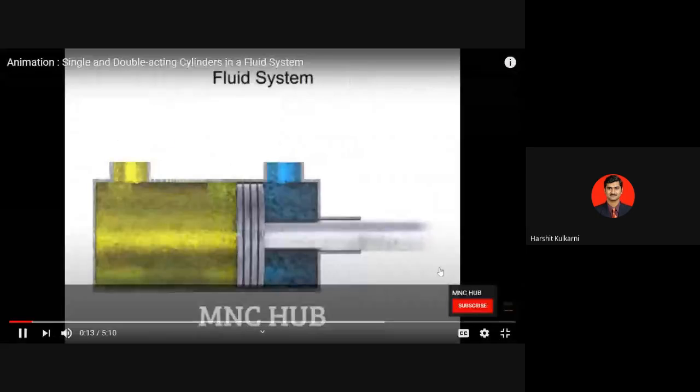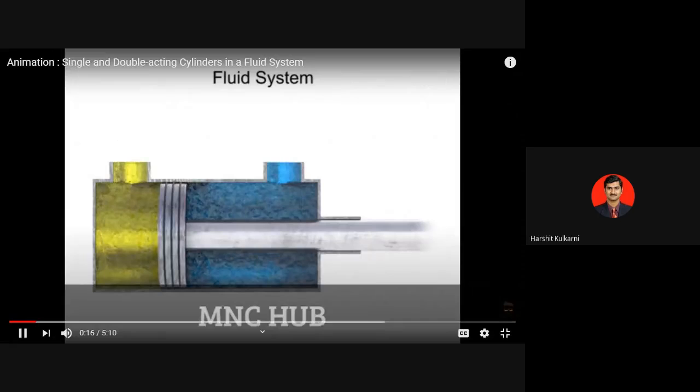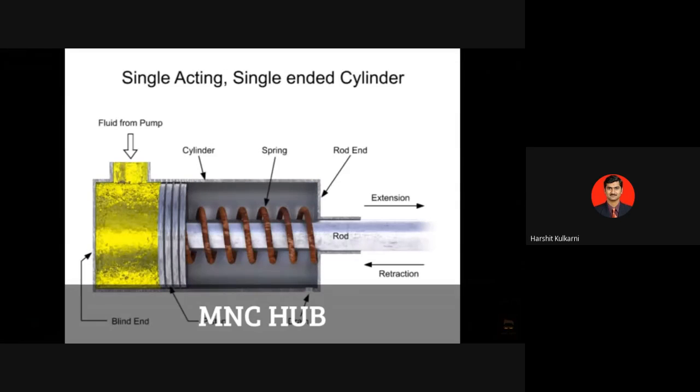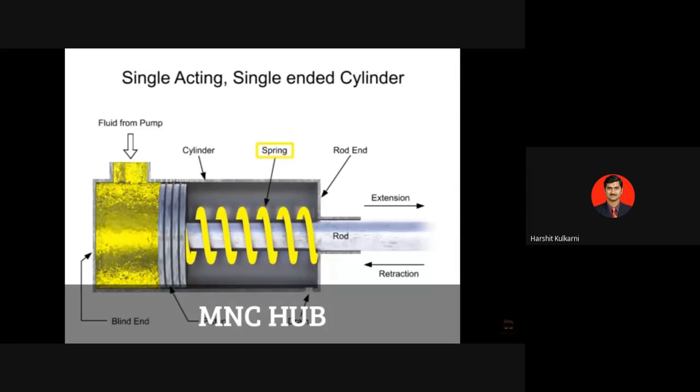Cylinder actuators deliver a linear push-pull motion via a rod and piston within a cylindrical tube. A single-acting cylinder is a cylinder in which the working fluid acts on only one side of the piston. The other side of the cylinder utilizes a mechanical load, springs, compressed air, other cylinders, or the momentum of a flywheel to push the piston back in the other direction. This particular cylinder utilizes a spring on the non-fluid side.